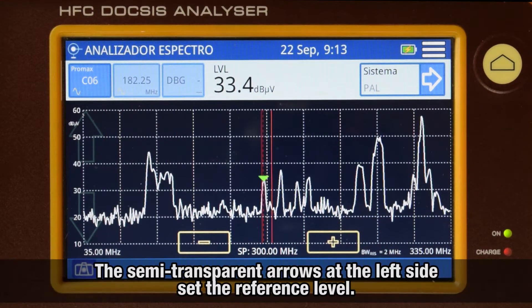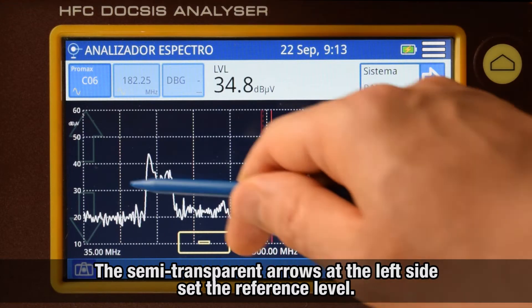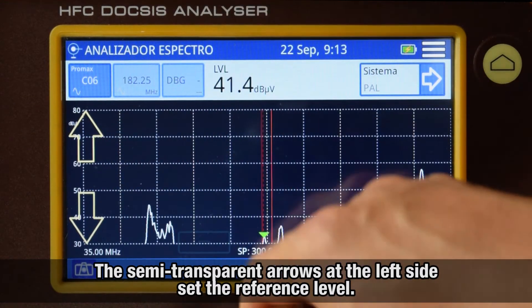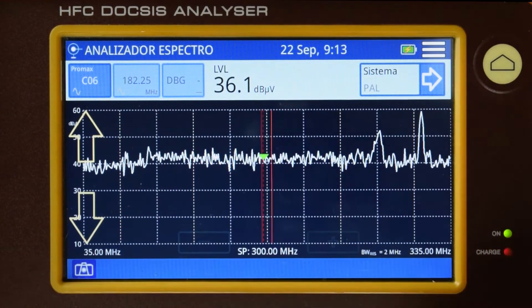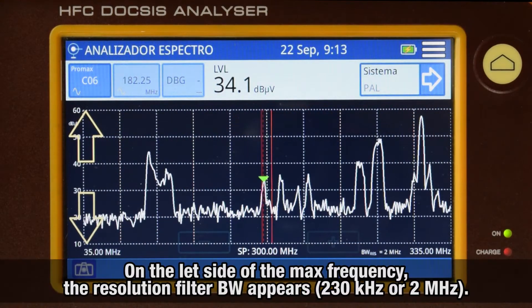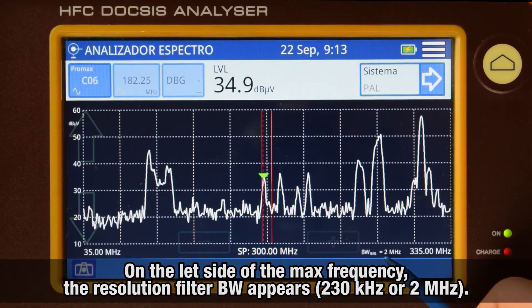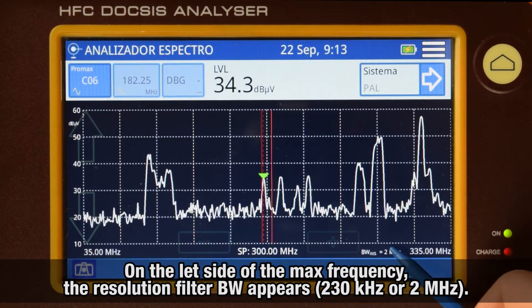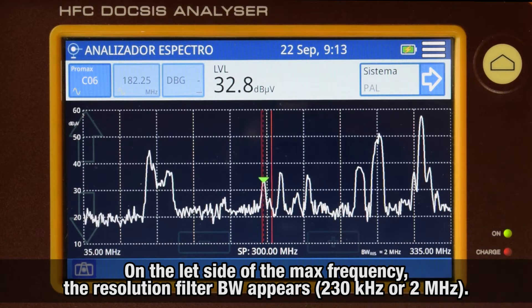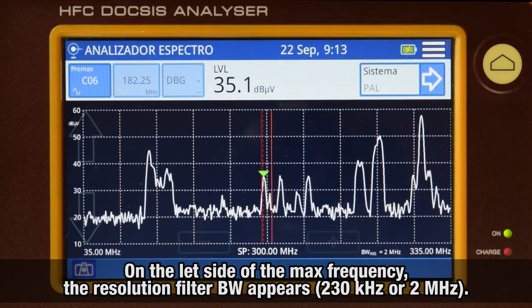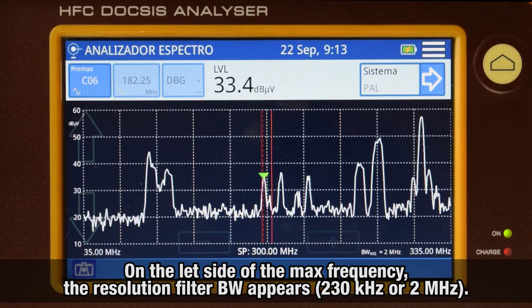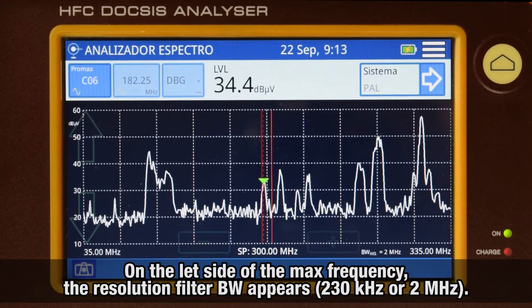In case we want to modify the reference level, we need to press the slightly transparent arrow-shaped buttons on the left side of the screen. On the left side of the maximum frequency shown by the analyzer on screen, the resolution filter bandwidth value appears, with its value being either 230 kHz or 2 MHz.